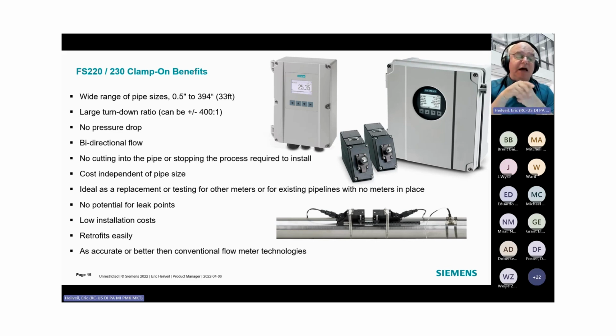Rod asks, what's the maximum allowed length of cable? Awesome, you're playing into my hand here. So there are two types of cables. There are the cables that we've been seeing here, which are the standard coax, and they could be quite long, depending on the type of meter. If it's an approved area, the maximum length is about 60 feet. But wait, there's more. Hold on. On an unapproved meter, they could be about 300 feet or more. But if you have the requirement to mount your transducers in an application that is hundreds and hundreds of feet away from the transmitter, it happens sometimes.